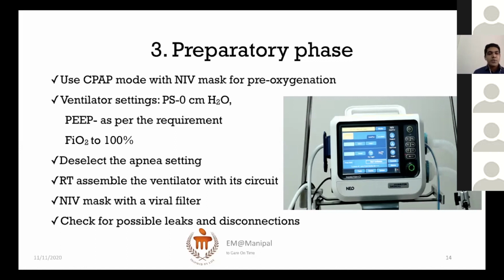Now, the ventilator has been set to a pressure support of 0 centimeters of water. Why 0 centimeters of water? It is to reduce the amount of aerosol containing viral particles disposed into the atmosphere during pre-oxygenation. The PEEP is kept at a minimum of 5 centimeters of water, and it can be adjusted as per the requirement. You can titrate it upwards until you reach a saturation of more than 90 to 95%. FiO2 is kept at a default of 100% for all patients during pre-oxygenation. At the end, you deselect the apnea setting so that it does not go to apnea mode during the pre-oxygenation time. It is the responsibility of the respiratory therapist to assemble the entire ventilator with its circuit.